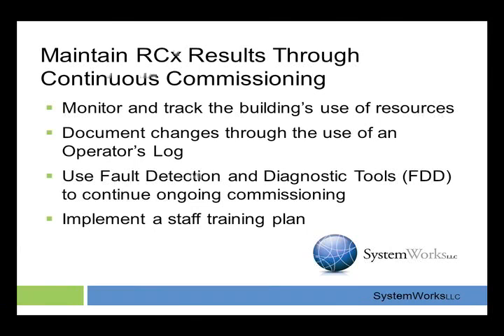So monitor and track the building's use of resources, and that basically means metering. It seems to be becoming more of the norm that building automation systems have utility metering that they are monitoring, so that you can see on a monthly basis and compare that to your utility bill. What are we using? When we adjusted this schedule, what did that do? What was the savings? So that you can continually tweak.